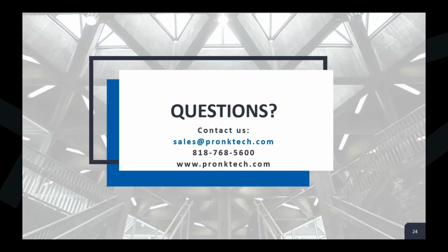My questions: when you're doing a PM and the equipment has a failure, so you check it as a failure, can you close that work order out as a PM failure generated to a corrective maintenance work order? And whenever you're testing equipment, can you distinguish between them? Because if you're doing a repair, you've got to test that equipment before it goes back out to the floor. Can you differentiate between this was a PM and this was a CM?